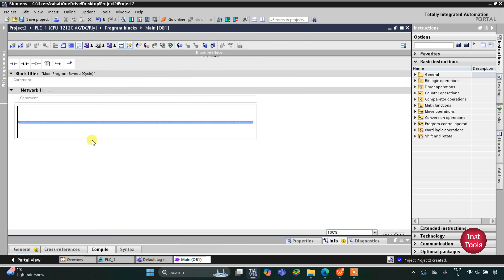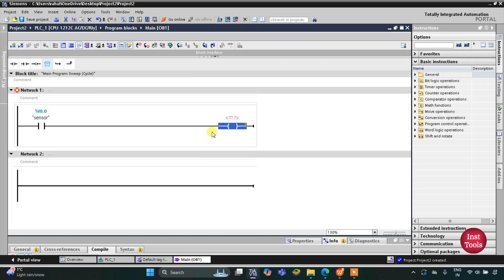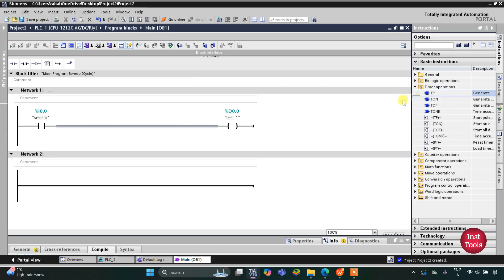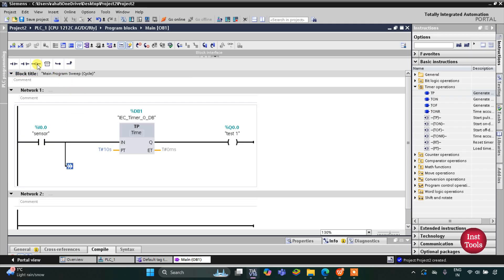Here we will draw the ladder diagram. First, when the sensor gets activated, Test 1 will run for 10 seconds, so there will be a TP timer operation here. The preset value for this TP timer will be 10 seconds. Then I will open a branch and add a coil.